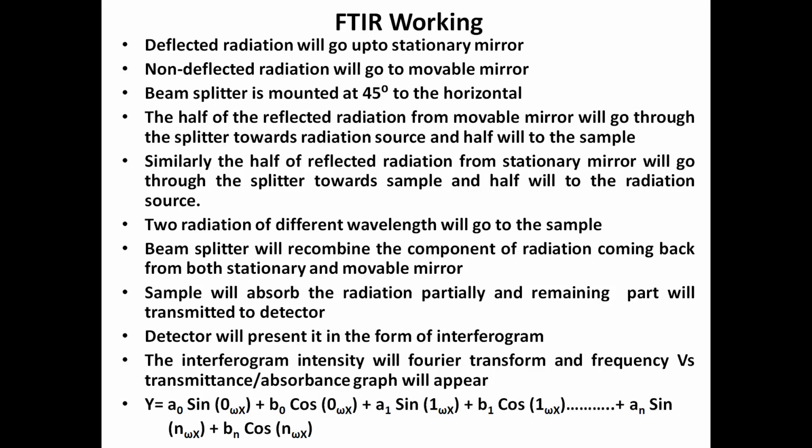So whatever information reaches the amplifier and computer will come in the form of an interferogram. Now, what is this interferogram? I am coming to that point. The interferogram intensity will undergo Fourier transform, and a frequency versus transmittance or absorbance graph will appear.